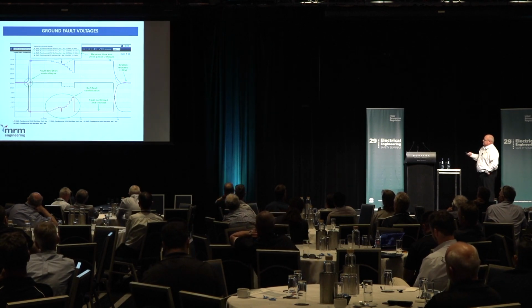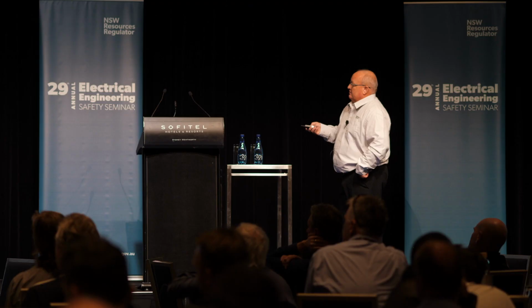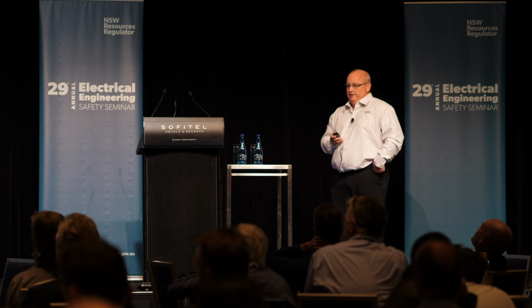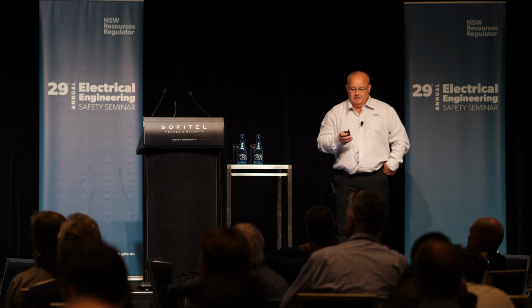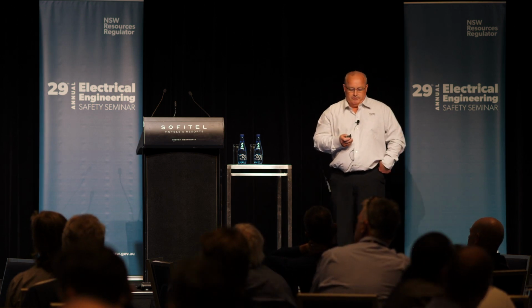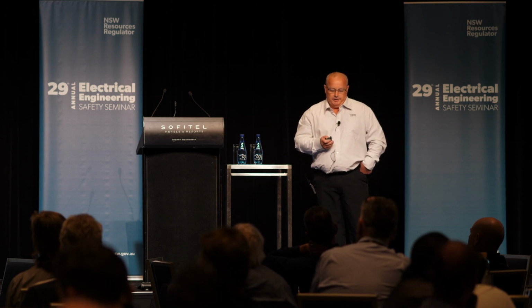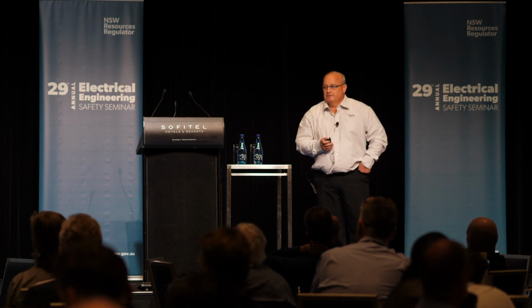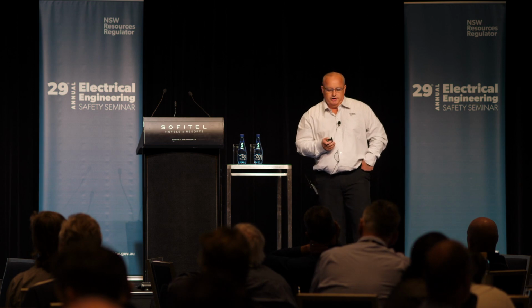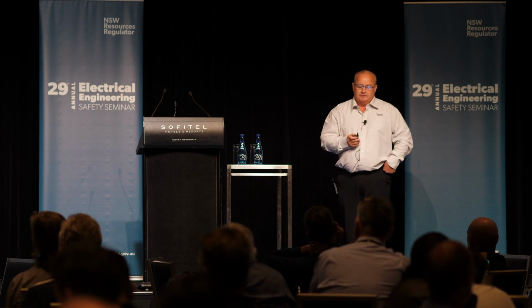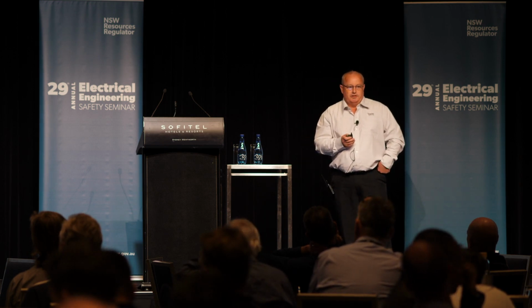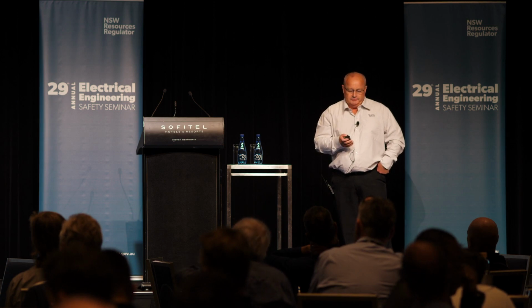One of the key things here is that the time they're using is going to be an extended time, where we're used to clearing a fault fairly quickly. The distribution authority can have up to like 30 seconds clearance time to actually allow their network to detect, do a directional test on the faults and then locate that fault and clear the fault rather than tripping the substation.